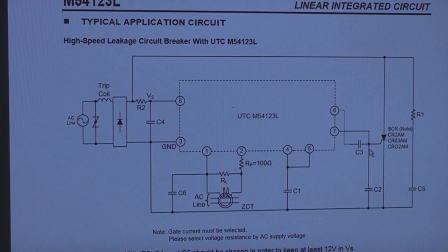Just as soon as it fires a pulse there, the whole thing goes short, puts a nice high current through that trip coil, and because of the way it's arranged, that current will sustain through that coil until the thing switches off. I would imagine that if it didn't trip, this coil would get quite hot quite quickly, but because the thing is on the far side of the circuit breaker, the idea is it will trip, but it means the coil will just keep trying until it does actually trip. This is just an MOV surge suppressor to avoid damage and false trips.